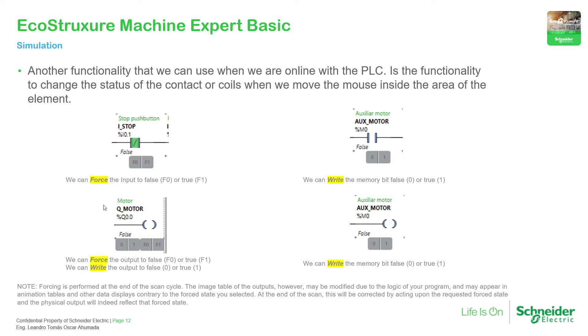It's important to know that when you write a value it can be overwritten by your own logic, so that is something you need to be aware of when trying to force or write a value. Even if you force a value it's going to be overwritten by your code, and the visualization can make you think your logic is working when it is not.